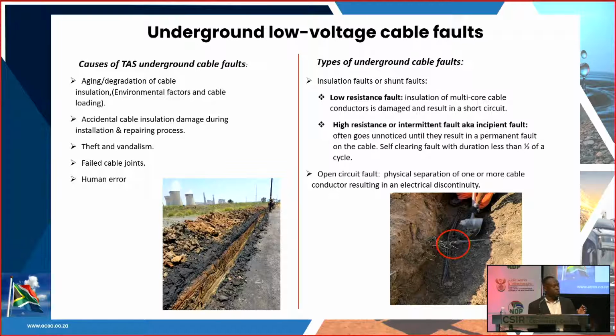And now, going to the area of interest, the faults that we can call high resistance or intermittent faults, also known as incipient faults. Incipient faults have the characteristic of self-clearing, meaning it's a fault that can occur for a short period and then clears itself automatically. So you won't be able to detect it because it happens for such a short period. Some scholars suggest that it happens for a period less than a quarter of a cycle. Some say less than half of a cycle. So you won't be able to detect it, but if it persists, then it will eventually lead to a permanent cable fault. And this is what we are interested in.